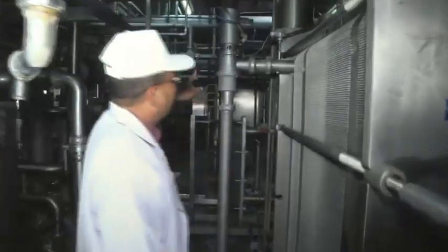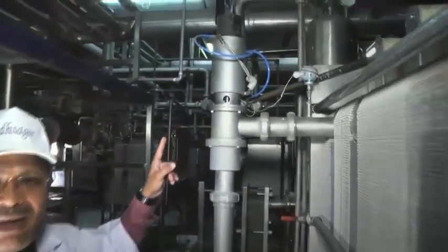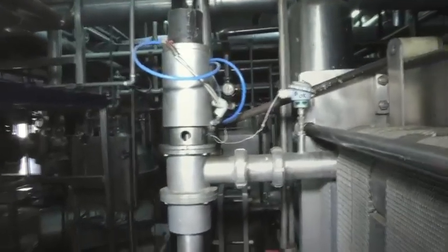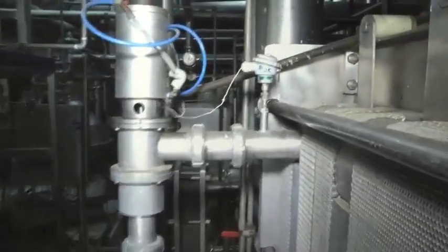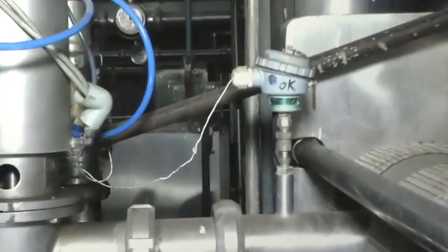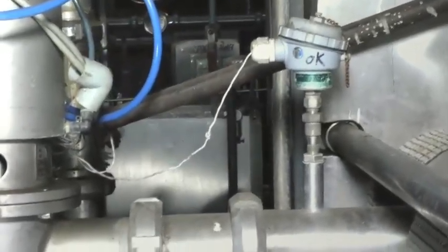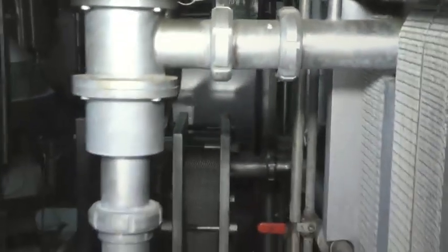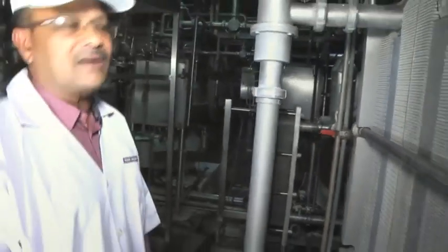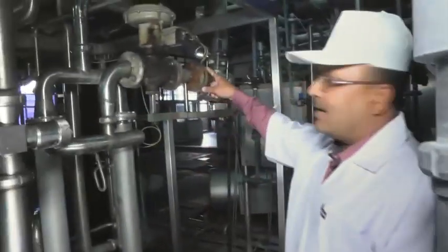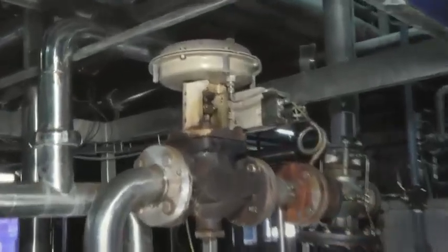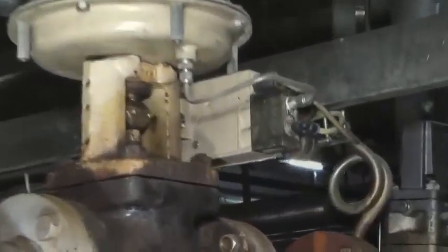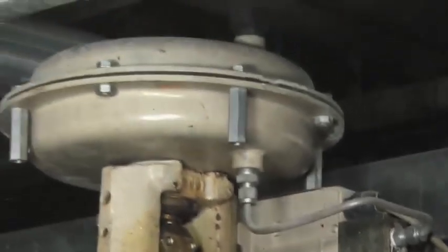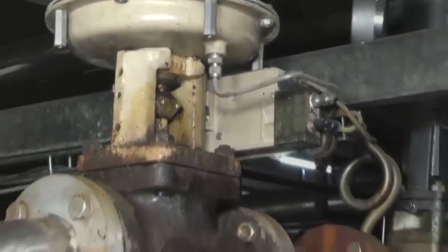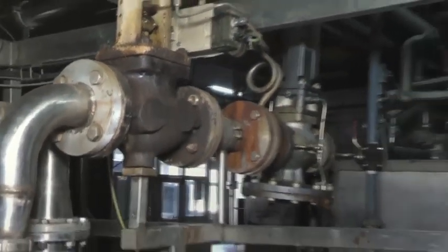Now, this is a diverter valve. The diverter valve is activated when the particular heating temperature goes below the set point, so that the milk comes into the recycle area. Now, this is a pneumatic valve. By means of the pneumatic valve, we can control the temperature according to the set point at the controller.